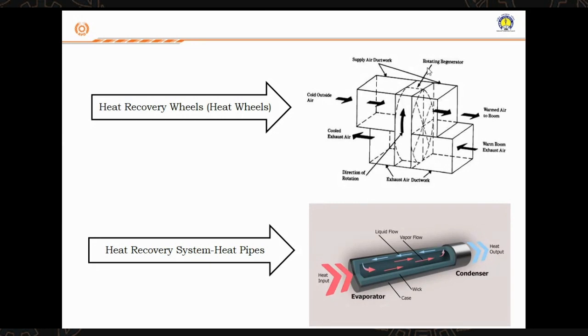So when this wheel rotates, the hot exhaust air moving from inside the room to outside heats the wheel. As the wheel rotates to the top, the cold ambient air coming from outside to inside gets heated. So you are recovering the heat with this heat wheel. These technologies have been implemented in almost all the hotels and software parks. Now you have a new waste heat recovery device called heat pipes. New in the sense that it is an established technology for large scale industries, but new for SMEs.